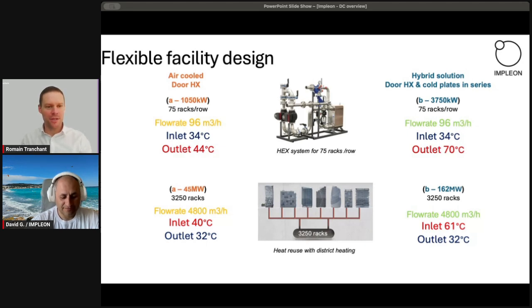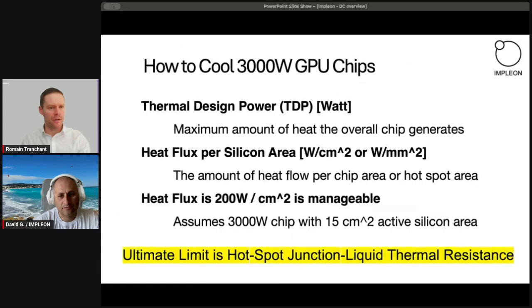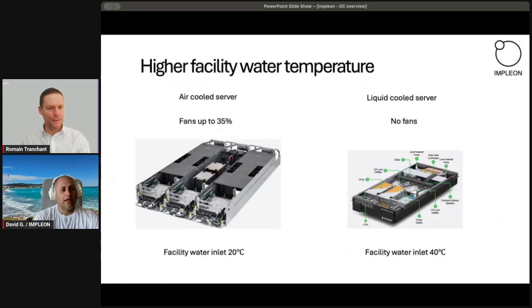You have in your presentation the simplification of the data center from moving from air cooled to liquid cooled. One of the things I didn't realize is that the fans of servers are using 10 or 20% of the energy of the facility. So fans inside of the server, I'm talking about these fans, they usually use around 5-10% of the energy of the server.